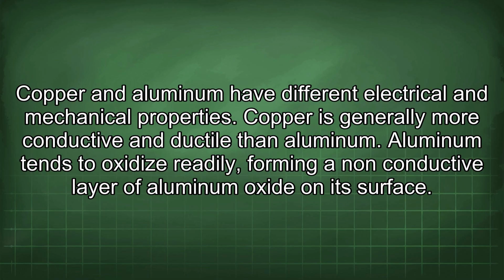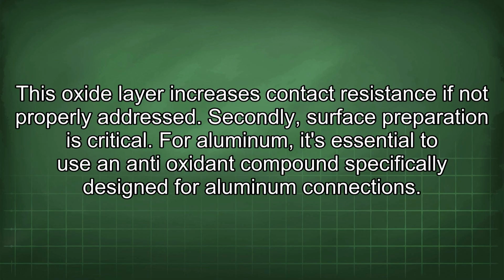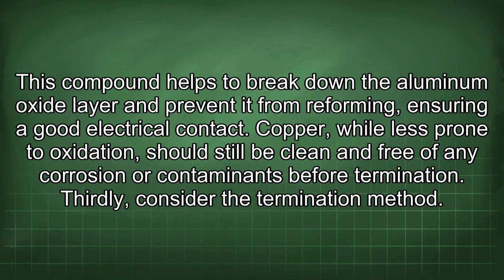Aluminum tends to oxidize readily, forming a non-conductive layer of aluminum oxide on its surface. This oxide layer increases contact resistance if not properly addressed. Secondly, surface preparation is critical. For aluminum, it's essential to use an antioxidant compound specifically designed for aluminum connections. This compound helps to break down the aluminum oxide layer and prevent it from reforming, ensuring a good electrical contact. Copper, while less prone to oxidation, should still be clean and free of any corrosion or contaminants before termination.